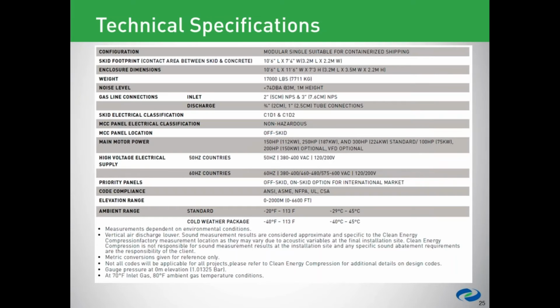Great. Rob is asking what type of heating is provided in the cold weather package. Sure. So I can't remember the type right off the bat, but it's an electric space heater with a fan on it that essentially heats up and circulates warm air through the compressor package. It's thermostatically controlled, kicks on automatically when the temperature drops below zero, and then automatically turns off once the temperature comes back up.